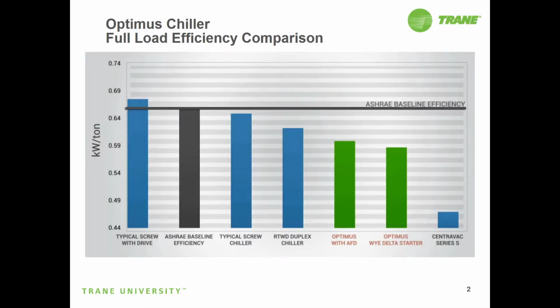This graph shows a comparison between ASHRAE 90.1 baseline efficiencies at full load and various operating efficiencies of other chillers. So let me explain this just a little bit. Over here on the left-hand side of the chart, we can see our kW per ton. And this is our ASHRAE baseline efficiency that we see right here. So the first column here is showing a typical screw with a drive. And remember, we're looking at full load efficiency comparisons here.